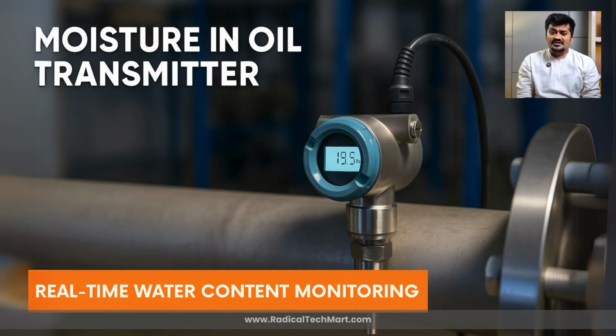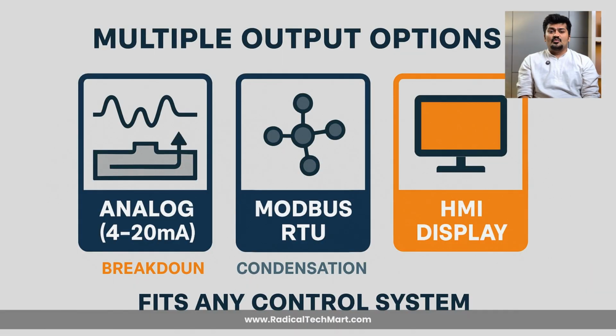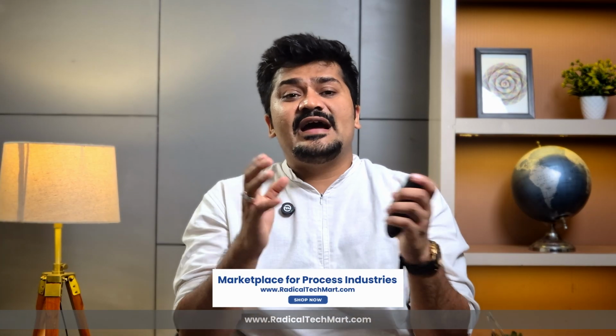Now let's cover what a moisture in oil transmitter is. A moisture in oil transmitter is a sensor that continuously measures the water content in oil, often in ppm, parts per million, or water activity. It typically uses capacitive polymer sensing technology, which reacts to the water molecules in oil and gives real-time data. The sensor can give output as 4 to 20 mA analog signals, Modbus RTU output for remote monitoring, or direct display via HMI or control panels. Some advanced models also measure oil temperature and dielectric strength.